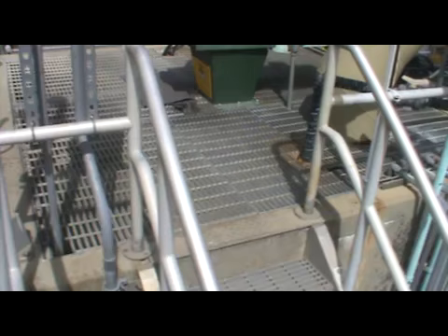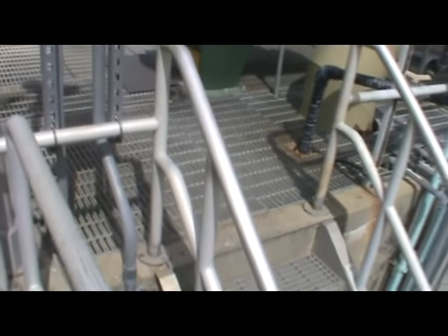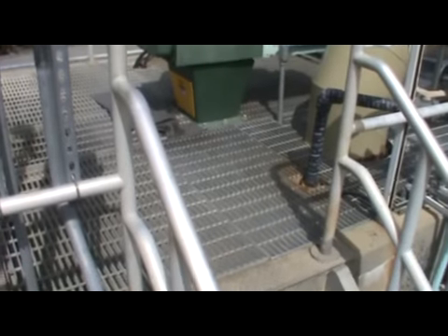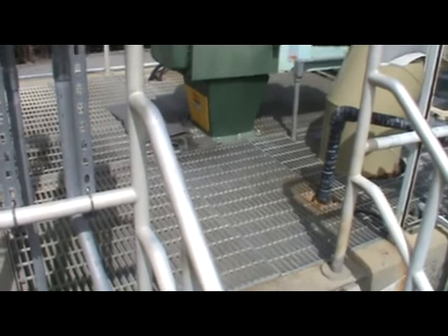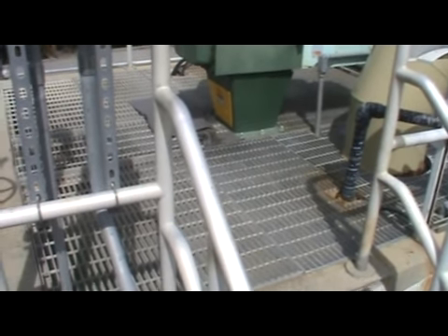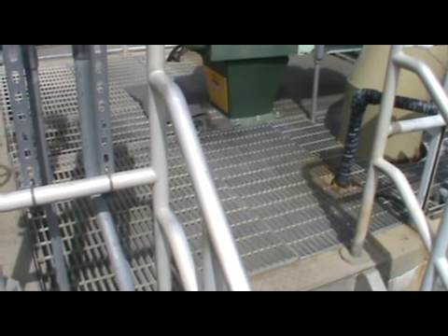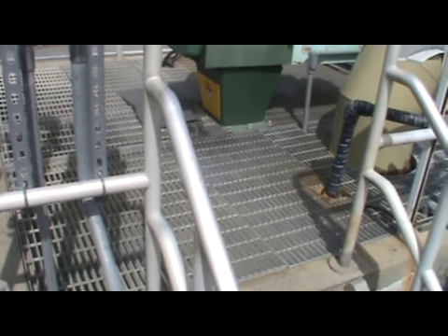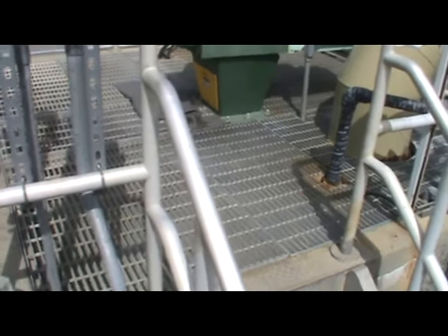So what's going on in this flash mix here is the alum, which has a positive charge, is added to the water, and it's being mixed together very, very vigorously. And what's happening is the water and everything in there is banging together, and the positively charged alum is banging around and collecting together with those negatively charged particles in the water and forming floc particles. There's a very exact science to this. Really, the water should remain in this flash mix for the coagulation process no more than about 30 seconds.